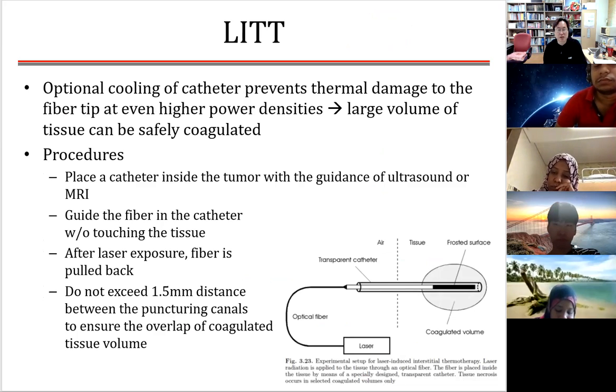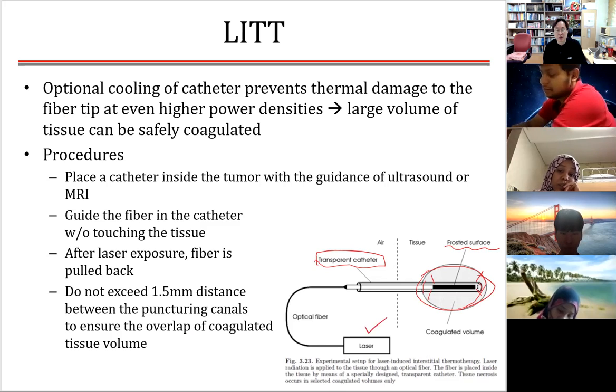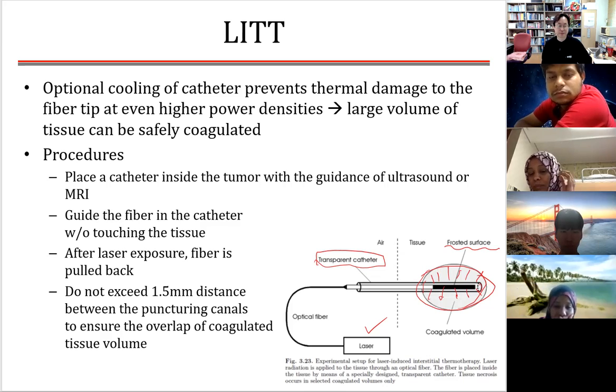And you have seen this one. The procedure is this. You place the catheter, the transparent catheter, into the tissue that you are targeting. Since the light will come out here, you want to place the catheter just within that range. Then you insert the optical fiber with a frosted surface to make the isotropic light delivery, and you turn on the laser. The laser will come out and generate heat, and the tissue will basically die. Once you are done with the laser exposure, you can pull the fiber back.